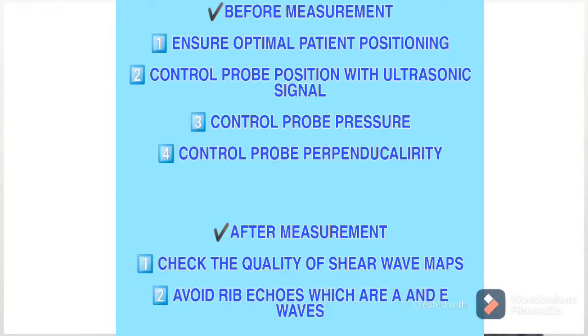In conclusion, before measurement, the physicians or doctors must ensure optimal patient positioning. Next, they must control probe position with the ultrasonic signal. Third, they must control probe pressure, and lastly, they must control probe perpendicularity. After measurement, we must check the quality of shear wave maps and avoid rib echoes, which are A and E waves.